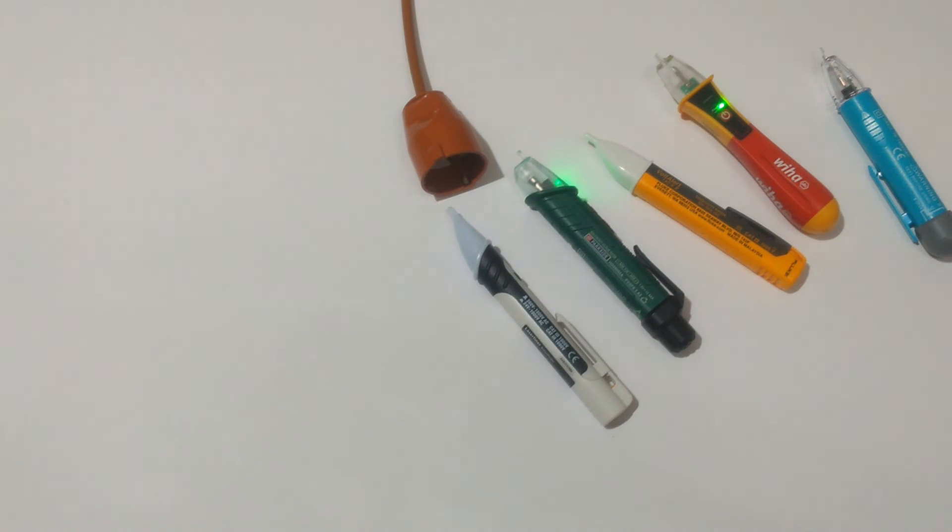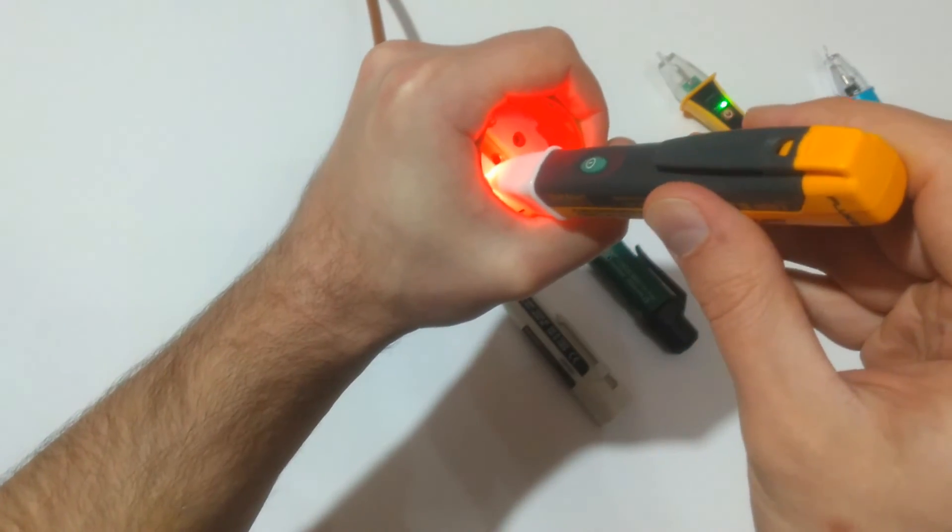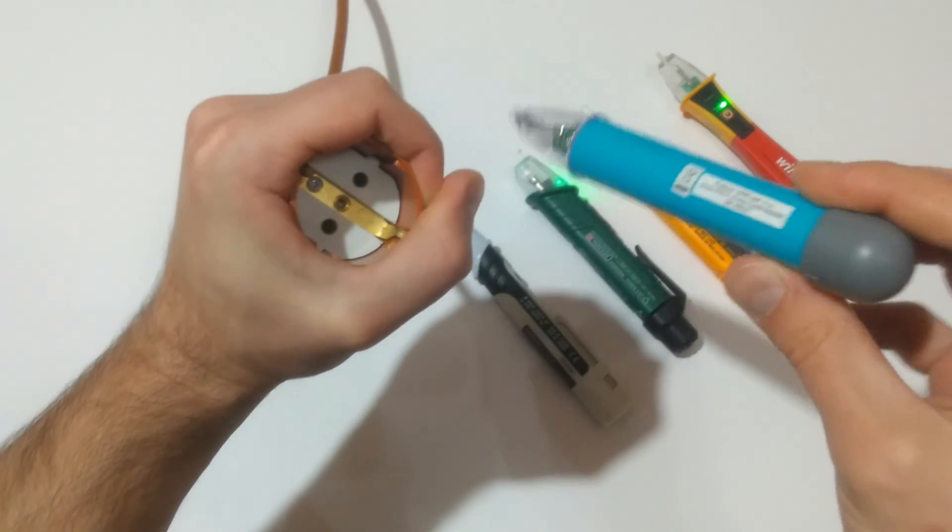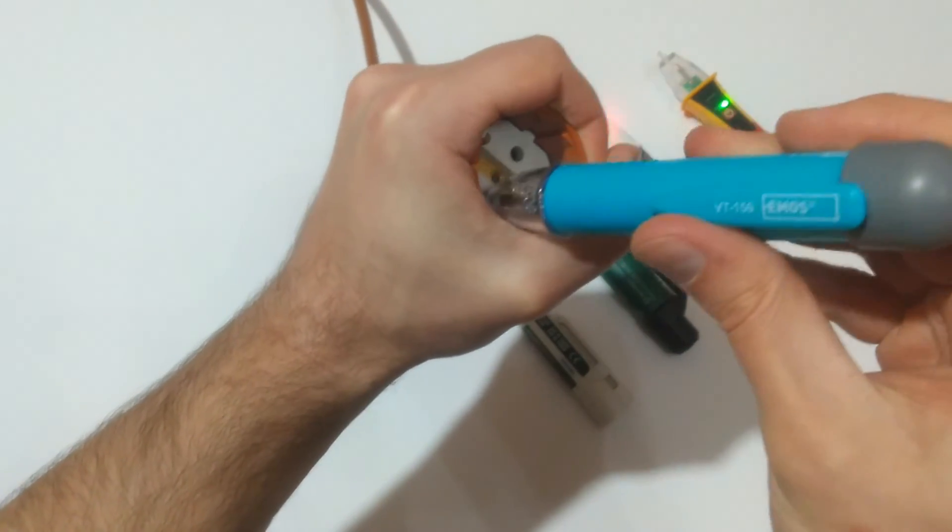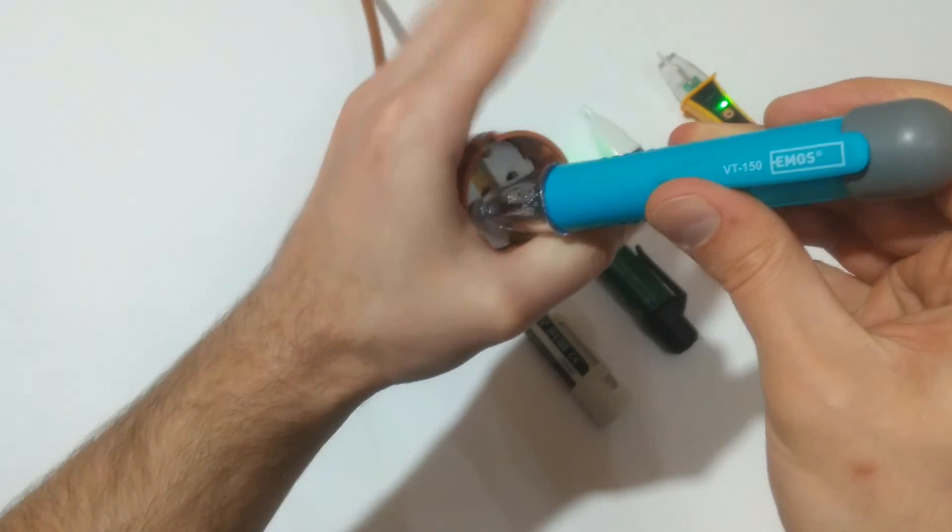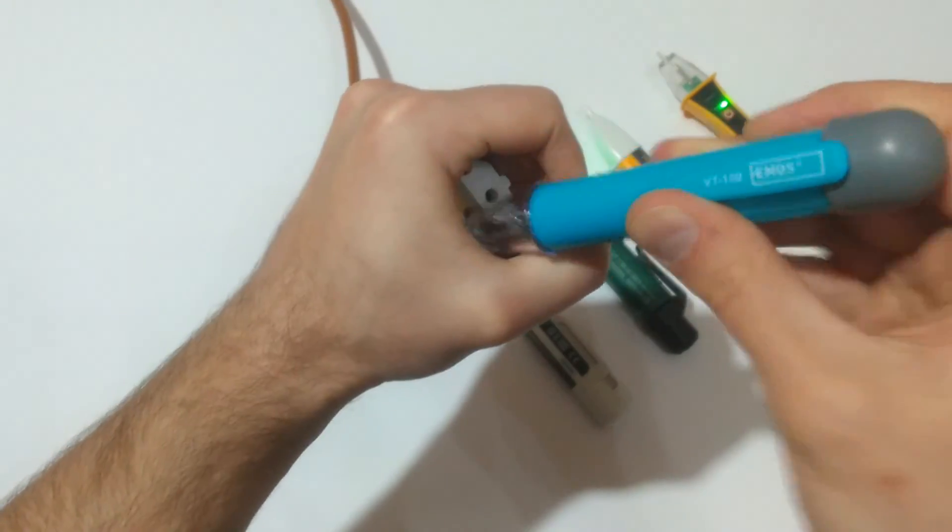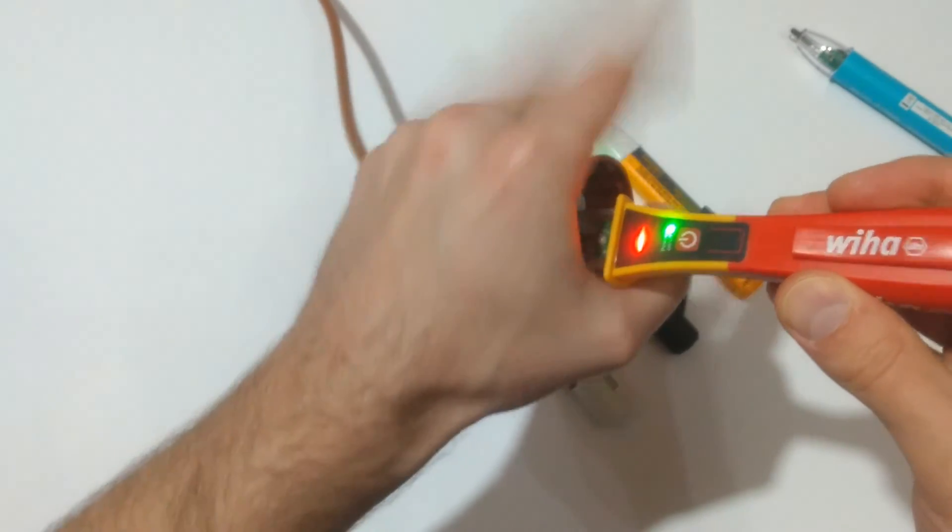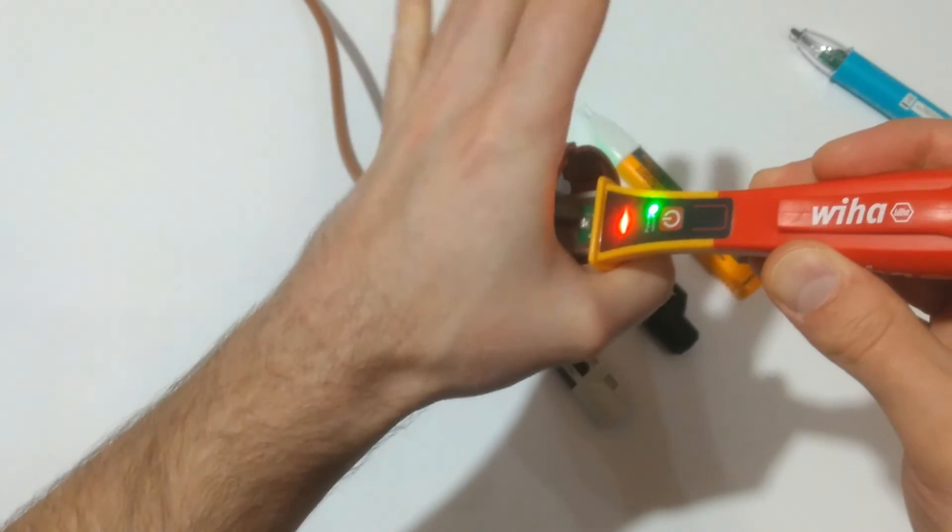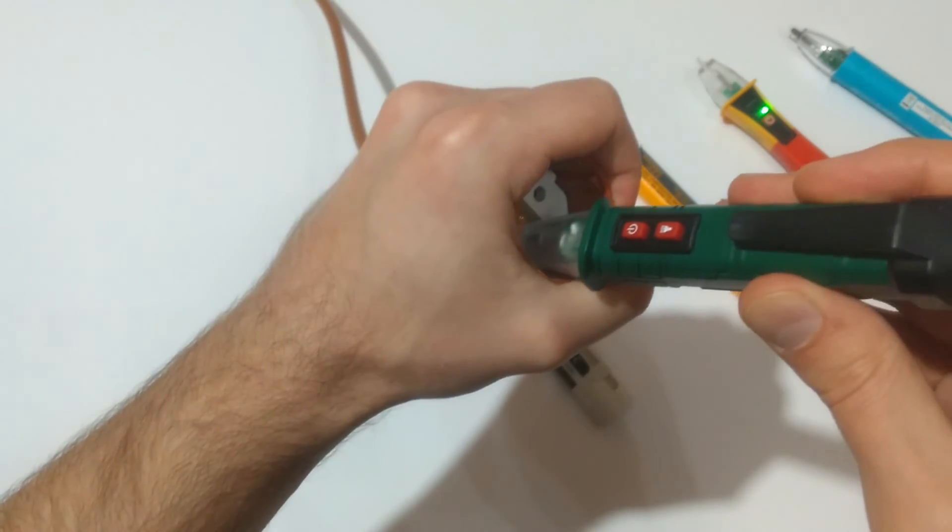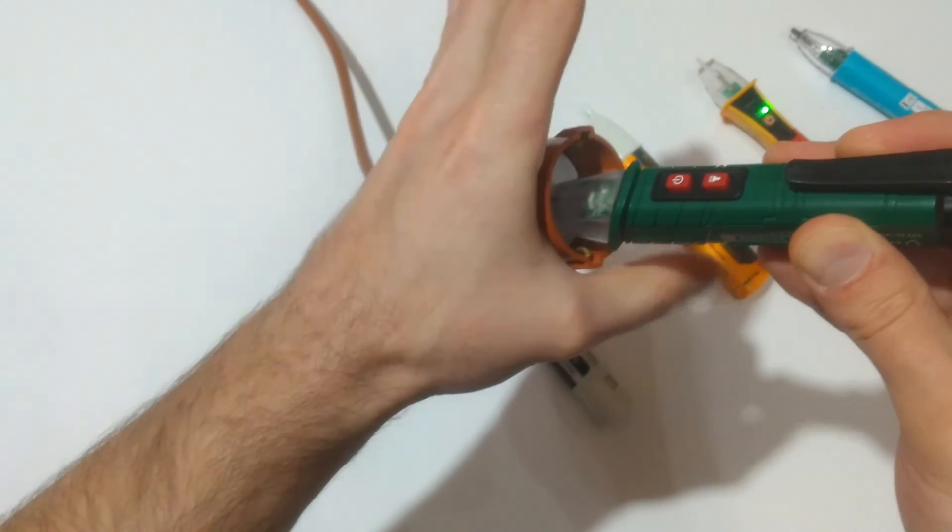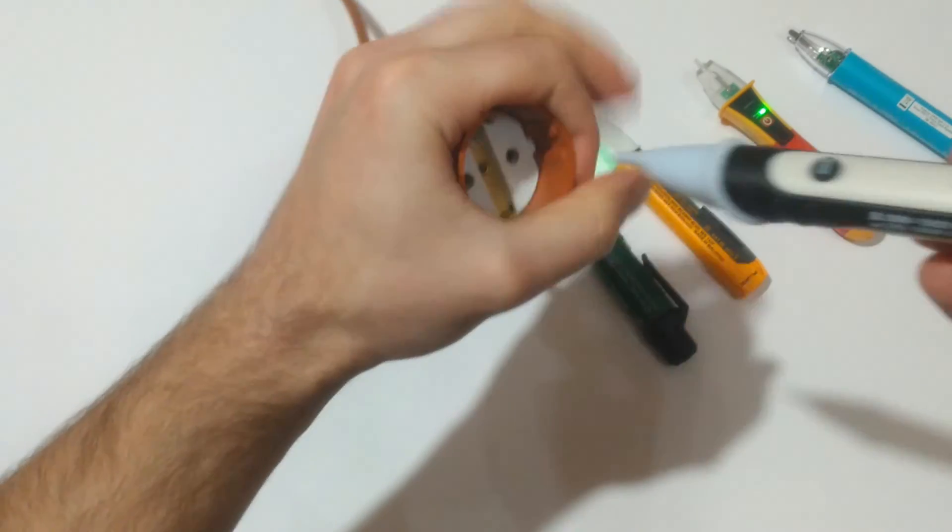Something interesting that I've noted is that some of these devices are affected by the position of your hand when measuring. Let me show you. So this here is the live conductor. The most affected device is this EMOS voltage detector. Nothing, nothing here, when I open my hand. Let's test the Wiha, no problems. Parkside, working correctly. Laser Liner.